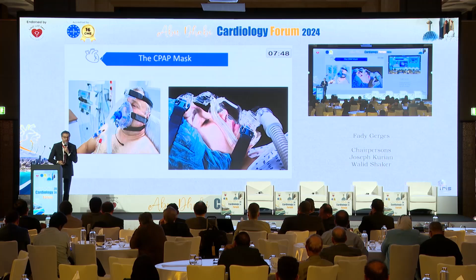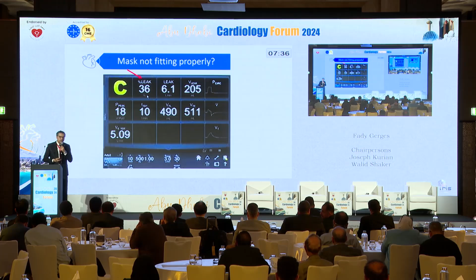And you can see that through the ventilator. For example, the ventilator can tell you the amount of leak. Like here, you can see the leak is 36%, and you can hear it with your ears near the mask if there's a leak.